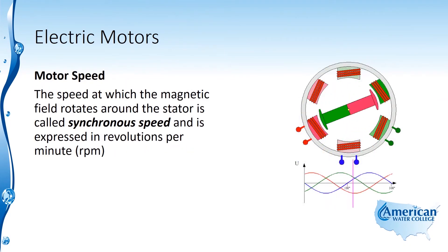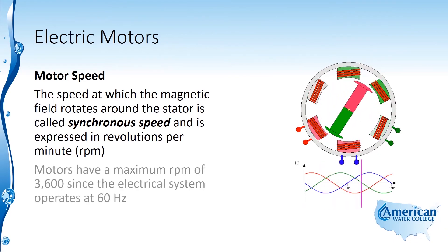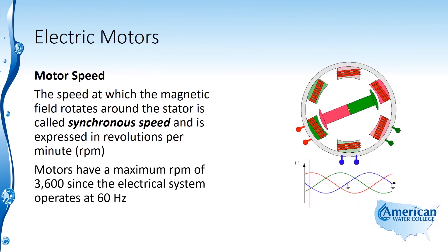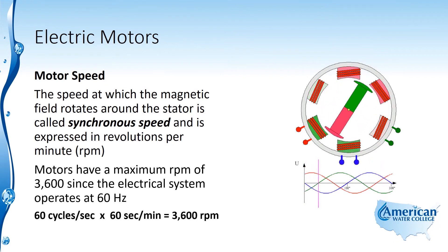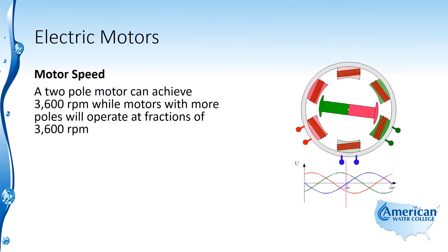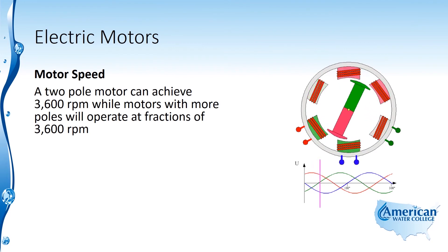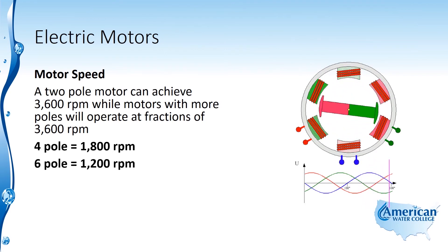The speed at which the magnetic field rotates around the stator is called synchronous speed, expressed in revolutions per minute, or RPM. Motors have a maximum RPM of 3600, since the electrical system operates at 60 Hertz — 60 cycles per second times 60 seconds per minute equals 3600 RPM. A two-pole motor can achieve 3600 RPM, while motors with more poles operate at fractions of 3600 RPM. For example, a four-pole motor operates at 1800 RPM, and a six-pole motor operates at 1200 RPM.